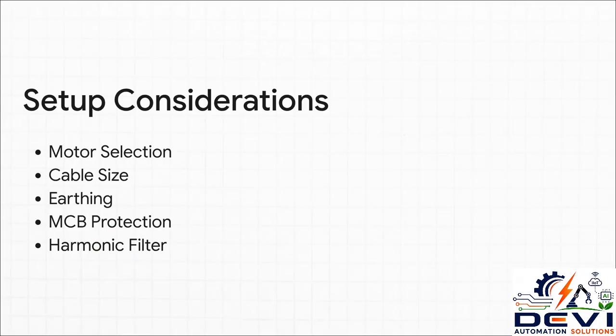To prevent those nightmares, you must follow critical installation steps. To all the PLC programmers and engineers tuning in, proper motor selection is non-negotiable. Ensure correct cable sizing to handle the current. Solid earthing is mandatory for safety and to prevent electrical noise. You also need proper MCB and MCCB protection against short circuits. And don't forget input and output reactors along with harmonic filters to keep your power grid clean and your drive functioning perfectly.